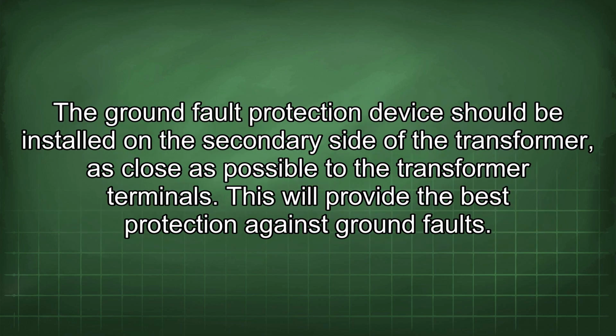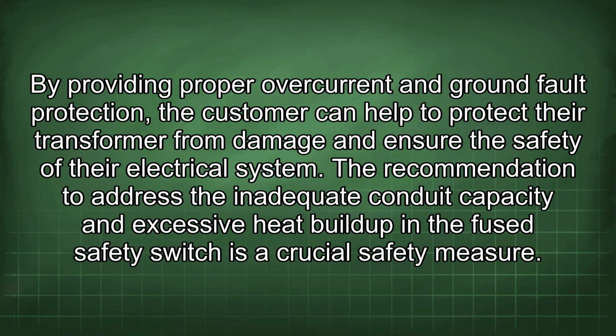The ground fault protection device should be installed on the secondary side of the transformer, as close as possible to the transformer terminals. This will provide the best protection against ground faults. By providing proper overcurrent and ground fault protection, the customer can help to protect their transformer from damage and ensure the safety of their electrical system.